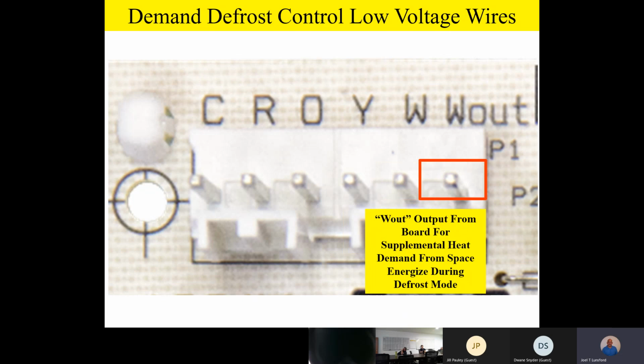Now the W out is an output. By the way, this is the only output from the board. This W out is an output from the board for supplemental heat demand from the space, and it's also going to be energized during defrost mode. So it serves two functions.